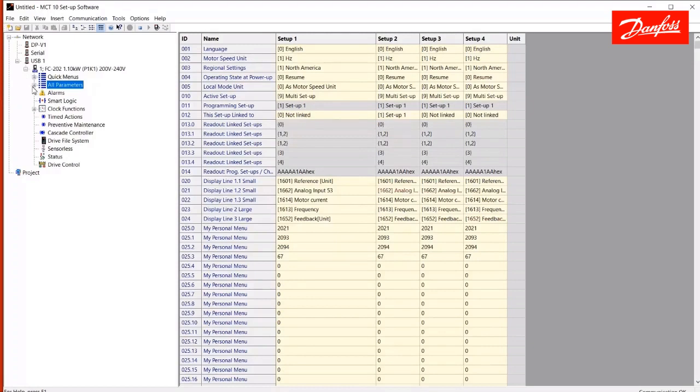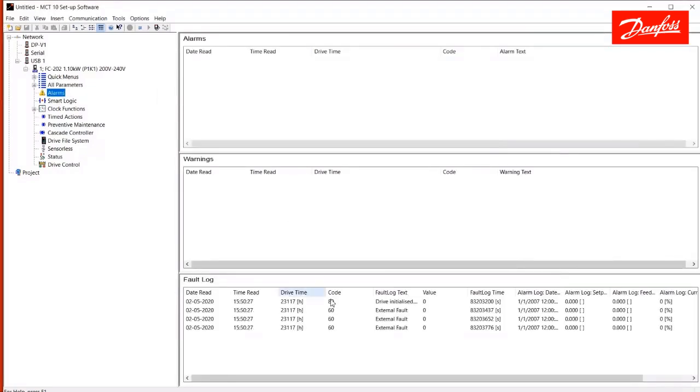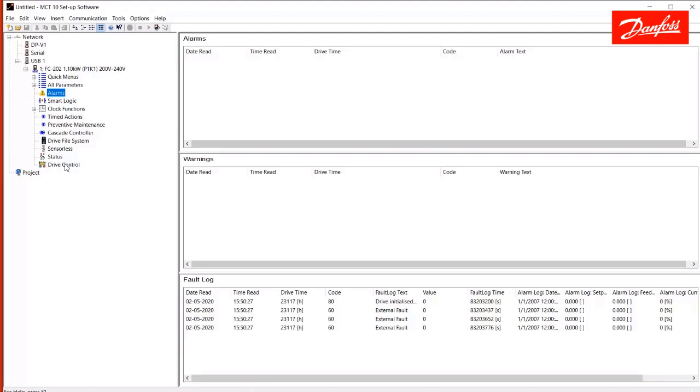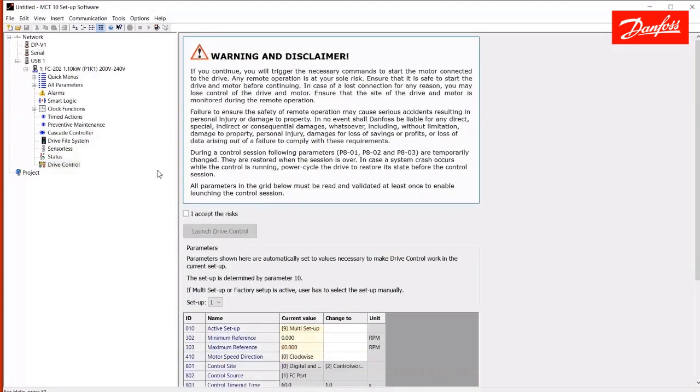So you can use the MCT10 software as an alternative to programming the drive to the keypad. What we have here underneath all parameters, I would consider help screens or wizards. Live access to the alarm log here by clicking that. This allows you to set the time and date from your PC and also set up time-based actions. We have a preventive maintenance wizard as well as some other things. Drive control here we'll talk about in another video that includes more advanced functions on MCT10. It allows you to control the drive remotely from your computer for testing and set up. So we'll get into that in a future video.